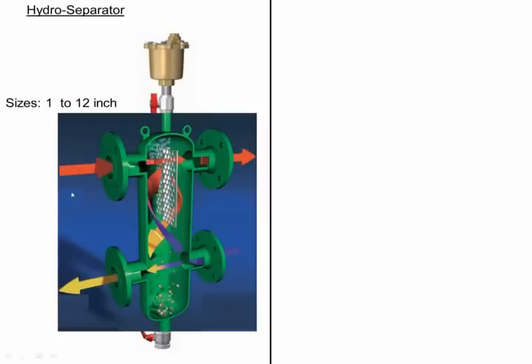What's going on on the inside of these separators? If you peel them apart, there are no moving parts. If you peeled it in half, this is what's happening. Here's a baffle plate. Now, the baffle plate is in there as a flow straightener.